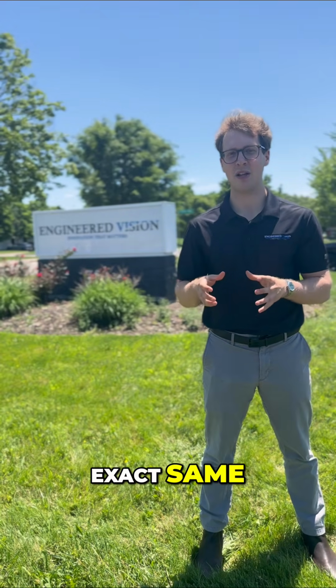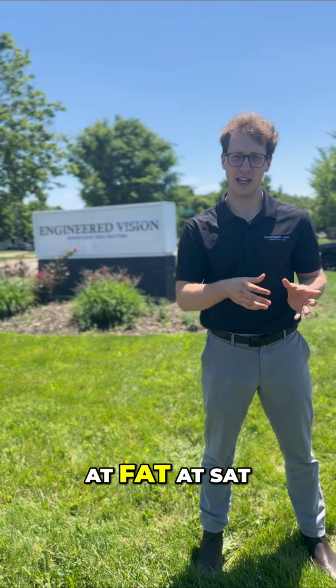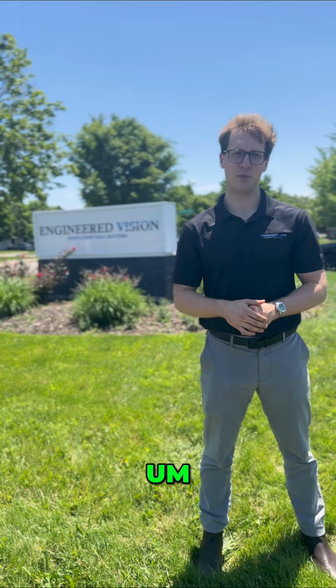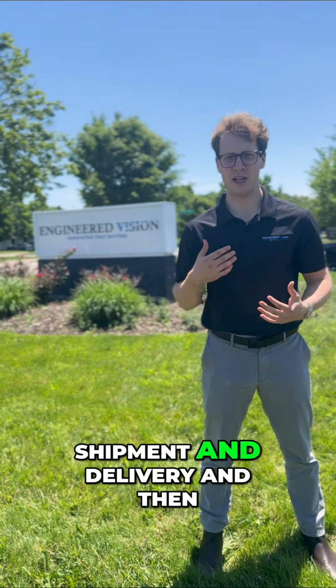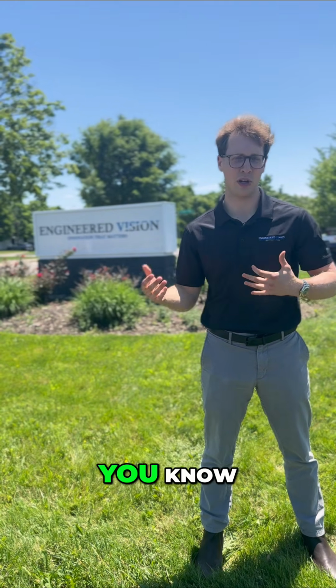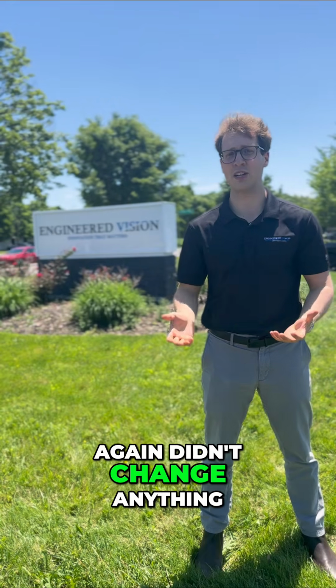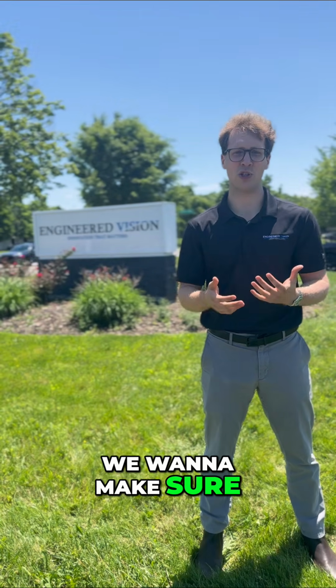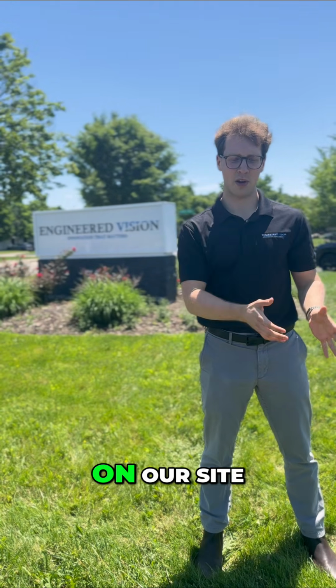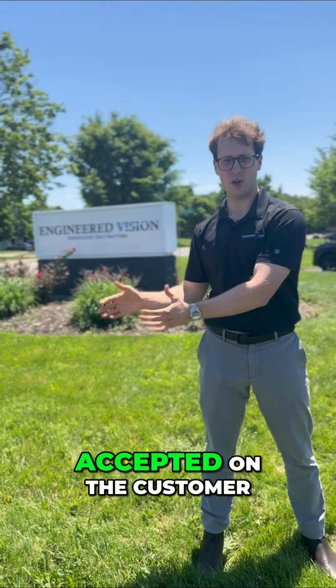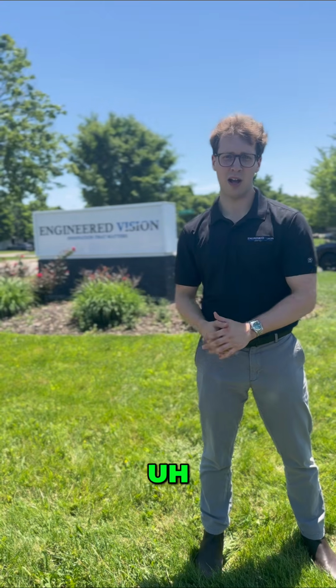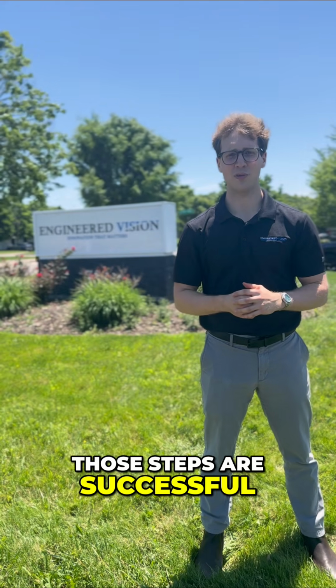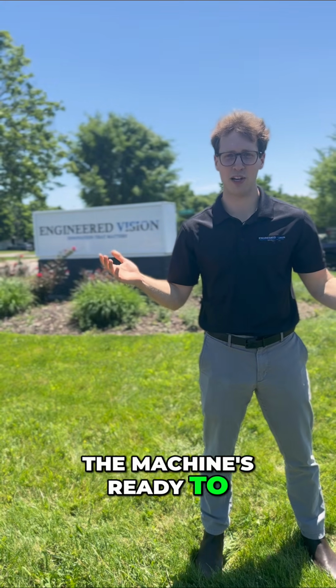We want to make sure that it's the exact same tests that we did at FAT, at SAT, to ensure that the shipment and delivery and then setting up the machine again didn't change anything about the machine. We want to make sure that it was accepted on our site and it should be accepted on the customer's site as well. And once both of those steps are successful, then the machine's ready to go into production.